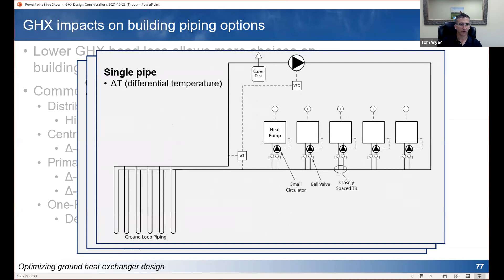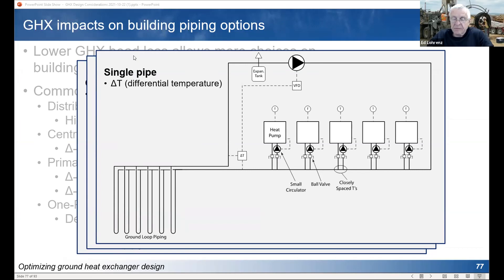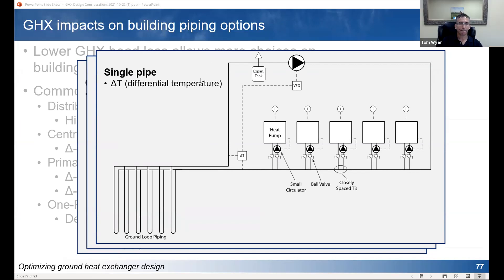The last common loop type in the geothermal industry is a one-pipe loop: a single pump sized for the entire ground loop plus the single-pipe building plumbing, with each individual heat pump using a small circulator to overcome head loss through just the heat pump and short local piping. These are all basic schematics — one important thing not shown is flushing and purging valves, which are required on every job. Flushing and filtering for good water quality is extremely critical to protecting the investment in high-end ECM pumps, particularly wet rotor ECMs, because of the very small gap between the rotor and the can.